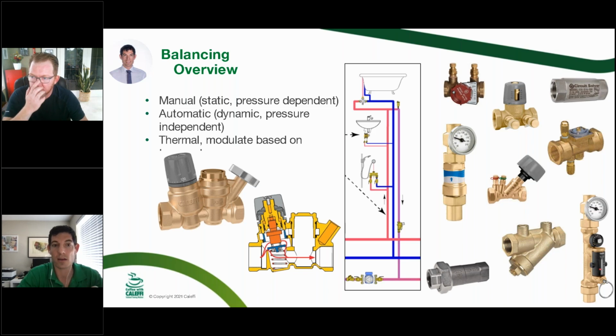Not theoretically, we should have X number of GPM through that riser, but if your demand is low, you start to close off those risers until they need it. And that's important for energy savings as well.